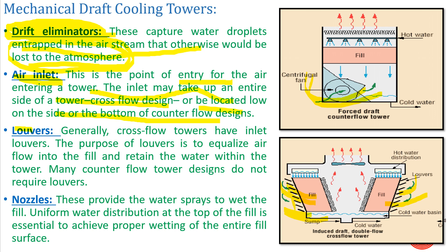Next is your louvers — the blackish parts that come outside the tower. The purpose of louvers is to equalize air flow into the cooling tower. We want the temperature of water to get cooled down evenly, so the airflow must be equalized to maintain uniform temperature drop. If the design of louvers is not proper, there may be chances your cooling tower doesn't perform as per requirements.